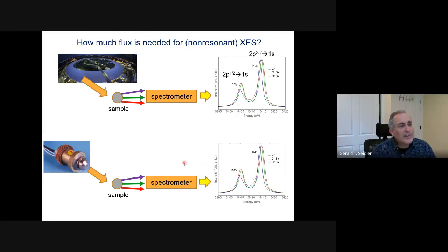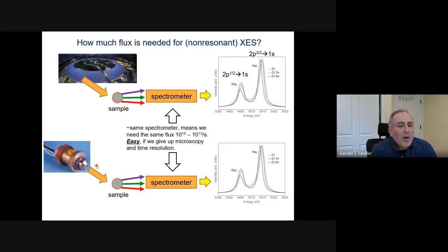I'm not going to reinvent the spectrometer. I'm going to use the same optics and the same general approaches at the synchrotron. So the only question is, how different is the incident flux? Well, the synchrotron lets you get a monochromatic beam with very high intensity, but even a not very big X-ray tube can give the same flux that's polychromatic. But all that matters is how many photons are above the binding energy of the element you're trying to study, rather than necessarily are monochromatic at that energy.